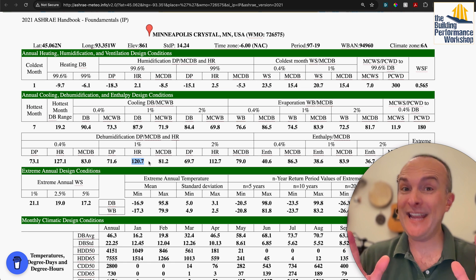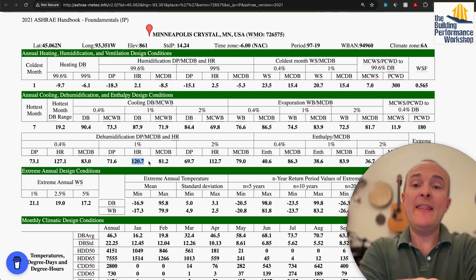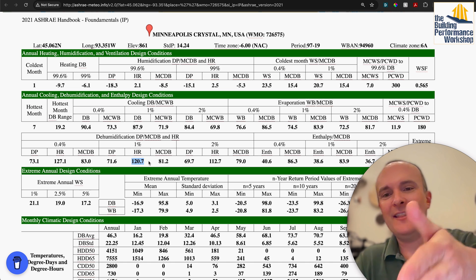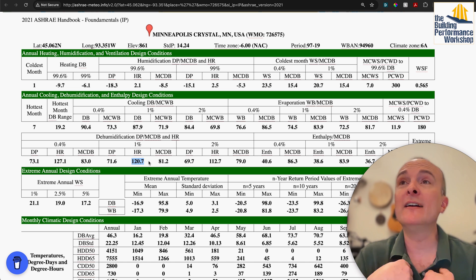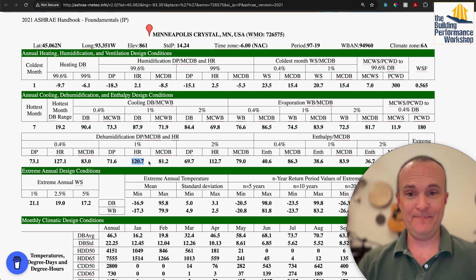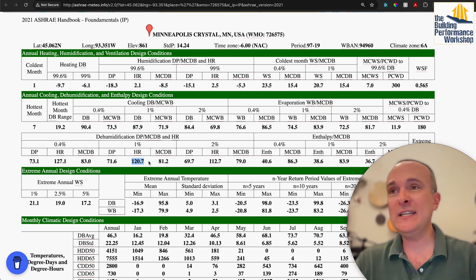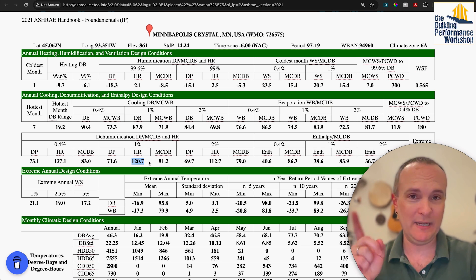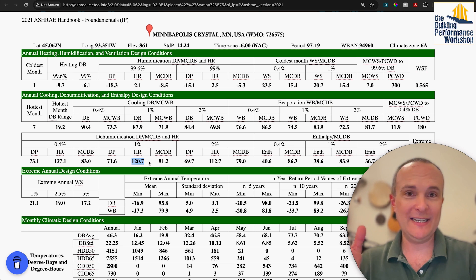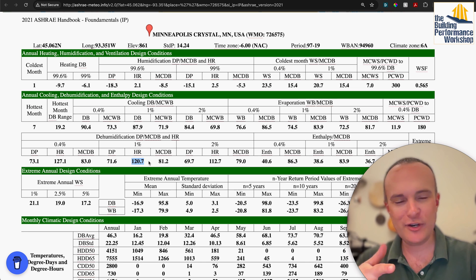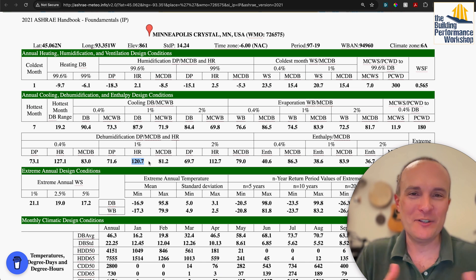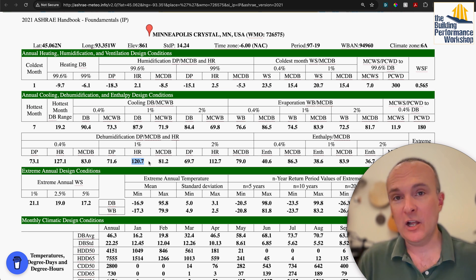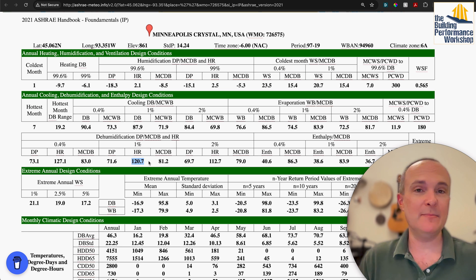That's Minneapolis in a leaky house. We also can't always depend on the air conditioner drying out the house. If the thermostat is set to 78 degrees and the outdoor temperature is 81 on a cloudy day, the air conditioner isn't running much. And if it was oversized to begin with — twice as much power as needed — it's going to short cycle, which causes major humidity problems in houses that might have worked fine in the past.